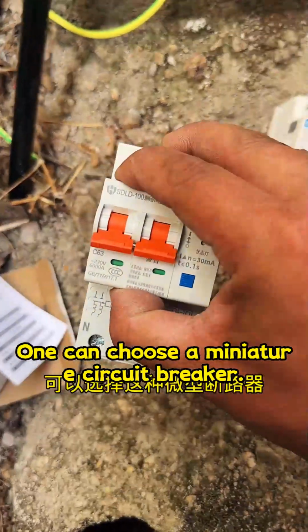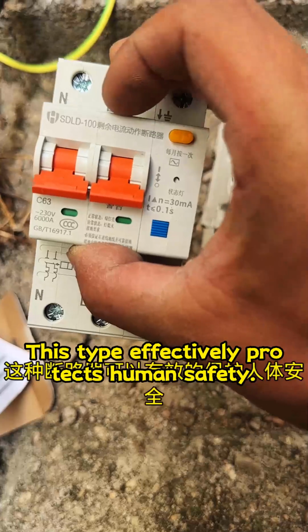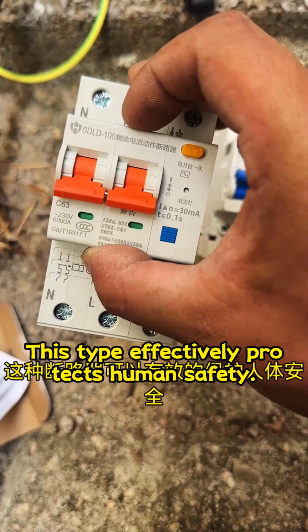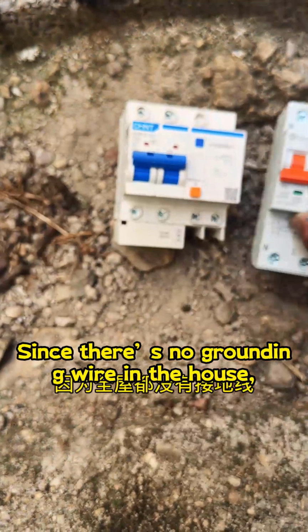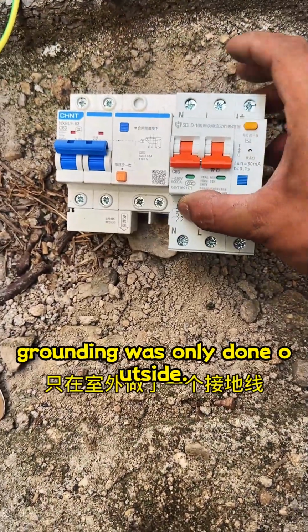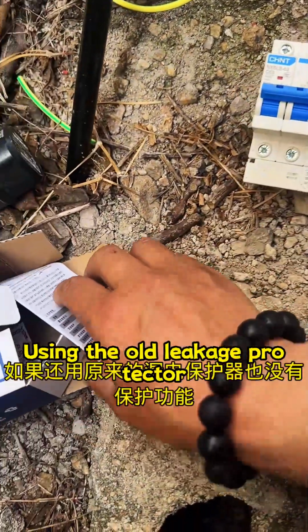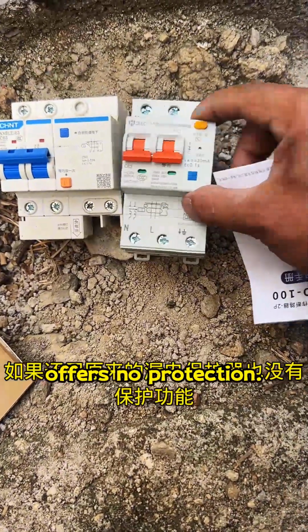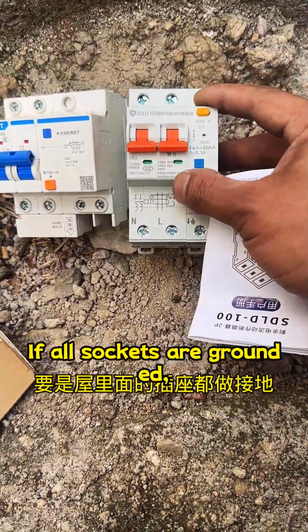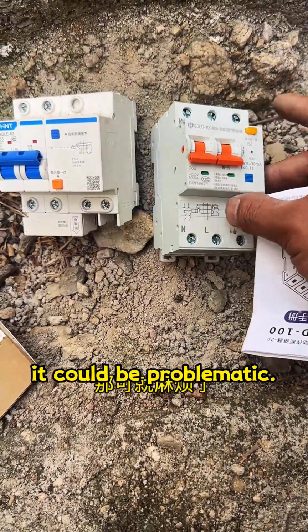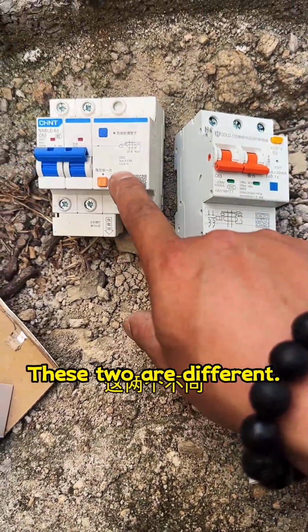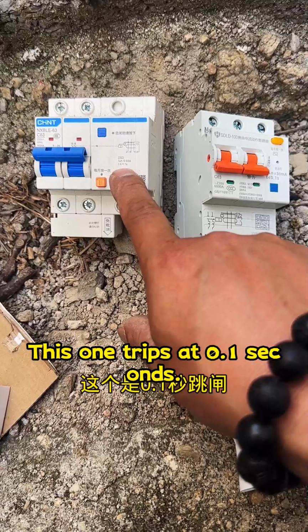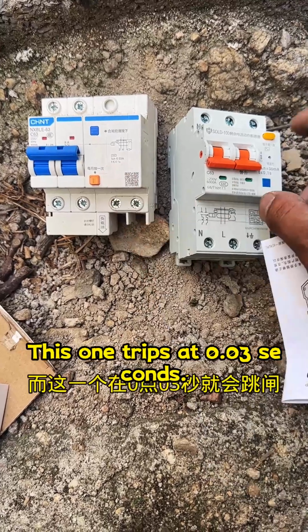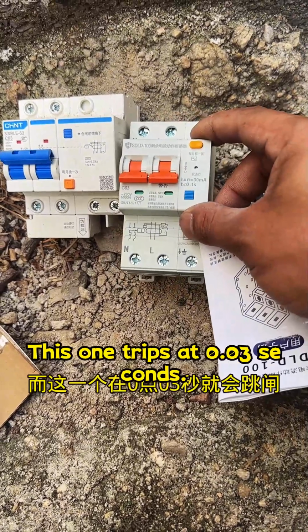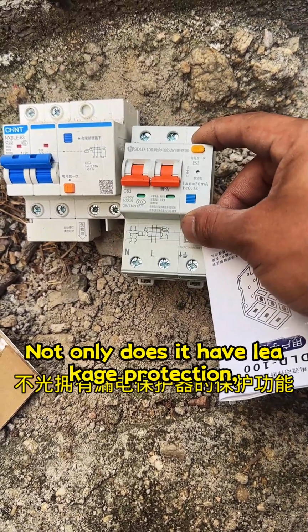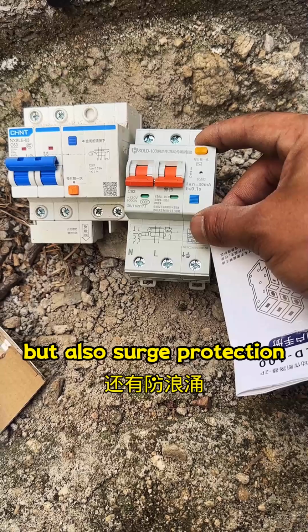One can choose a miniature circuit breaker. This type effectively protects human safety. Since there's no grounding wire in the house, grounding was only done outside. Using the old leakage protector offers no protection. If all sockets are grounded, it could be problematic. These two are different. This one trips at 0.1 seconds. This one trips at 0.03 seconds. Not only does it have leakage protection, but also surge protection.